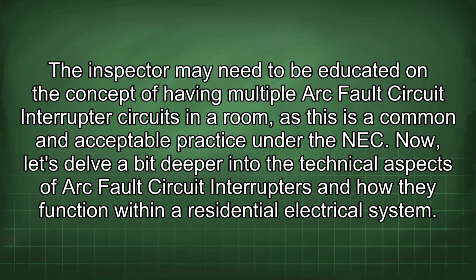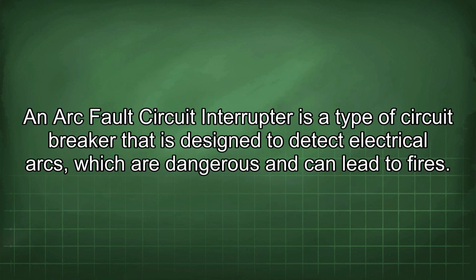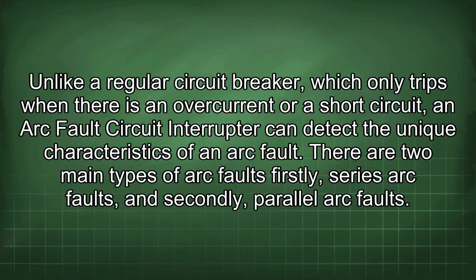Now let's delve a bit deeper into the technical aspects of arc fault circuit interrupters and how they function within a residential electrical system. An arc fault circuit interrupter is a type of circuit breaker that is designed to detect electrical arcs, which are dangerous and can lead to fires. Unlike a regular circuit breaker, which only trips when there is an overcurrent or a short circuit, an arc fault circuit interrupter can detect the unique characteristics of an arc fault. There are two main types of arc faults: firstly, series arc faults, and secondly, parallel arc faults.